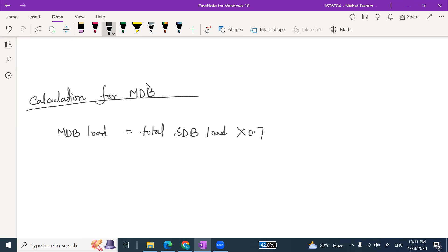So MDB load equals to total SDB load into 0.7, plus EMDB load into 0.7, plus pump load into 0.7. So total SDB load is basically 12 into 1 SDB load.